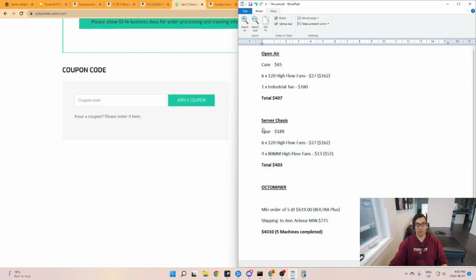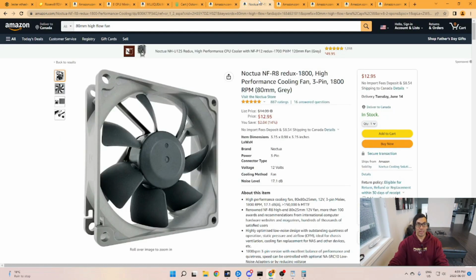The base purchase for a server chassis build is about $400, which seems expensive compared to a $65 case. But if you don't manage heat flow, you'll have to shut things down in summer, costing you money long term. A lot of YouTubers show open air rigs, which are cheaper, but not efficient since you can't guarantee a cold aisle and a hot aisle. We just need to cool the front aisle and exhaust the back aisle.